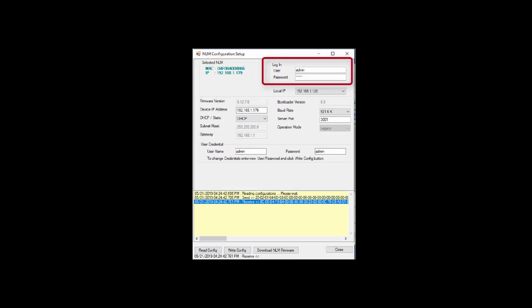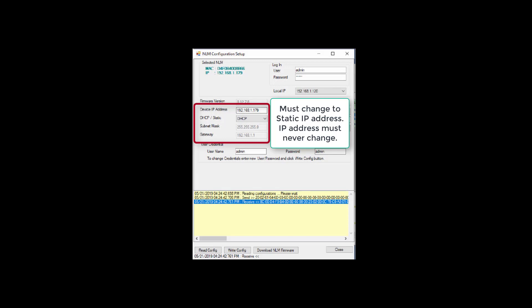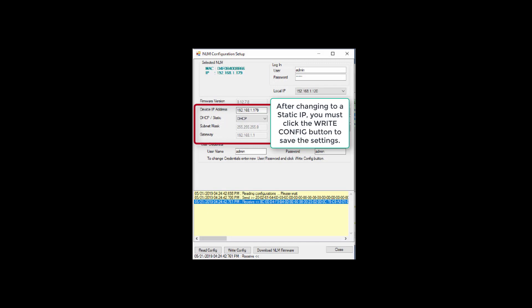The top right shows the login credentials for the utility. If you have not changed them, they should be Admin and Admin. Below is the local IP address of the computer with the Universe Finder utility. Below the unit information, the current Ethernet firmware in the unit will display. If this needs to be updated, click the Download NLM Firmware button and download an updated firmware image. Next is the current IP address programmed into the device. The box below will state if the IP address was supplied from DHCP or if it is a static IP address. Since the IP address must never change, if it is supplied by DHCP, you must program in a static IP address, subnet mask, and gateway IP address.